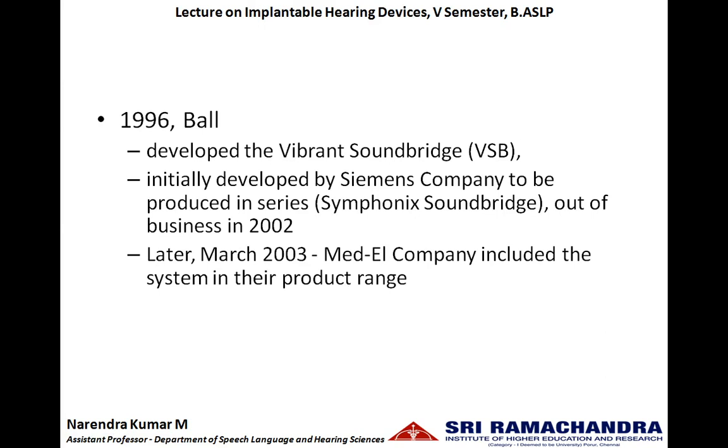In the year 1996, Ball developed an equipment called the Vibrant Sound Bridge. It was initially developed by Siemens company under the name Symphonix Sound Bridge, and it also used an electromechanical transducer. Later, the MED-EL company took it over in the year 2003 as the Vibrant Sound Bridge. It is a partially implantable hearing aid. The external audio processor consists of the microphone, amplifier, and sound processor. The internal device consists of the internal receiver, a conductor link, and the floating mass transducer, which can be placed at any part of the middle ear. Depending upon the incoming change in electrical energy, this floating mass transducer starts to vibrate.